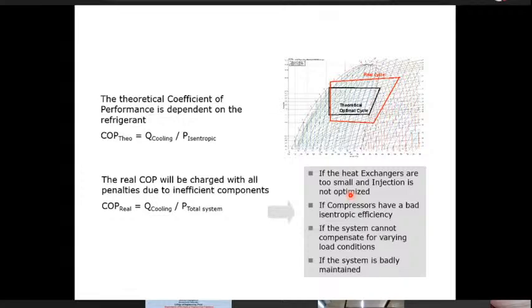The system not able to compensate for varying load conditions. It's essentially an air conditioner. If you buy a 1.5 ton air conditioner for your bedroom, you cannot be sure that the load is going to be 1.5 ton all the time. There will be days when it will be less, and there could be a few days when it might exceed for a few hours.